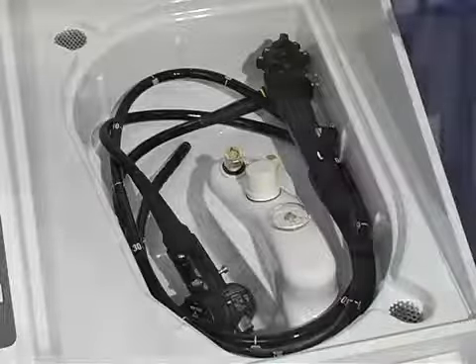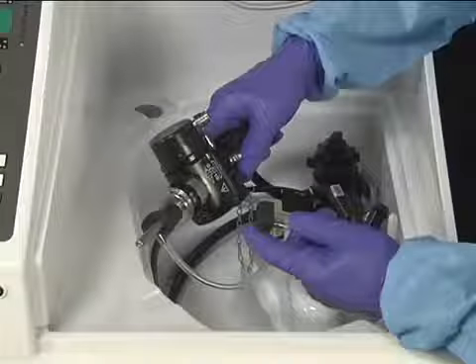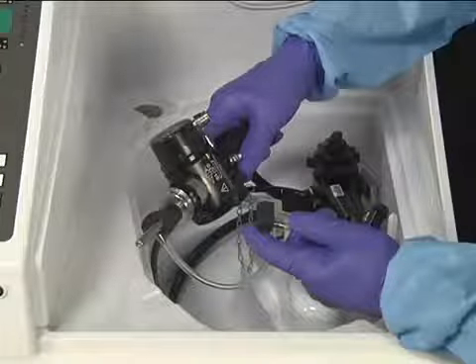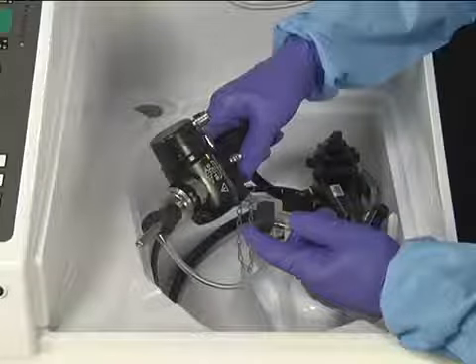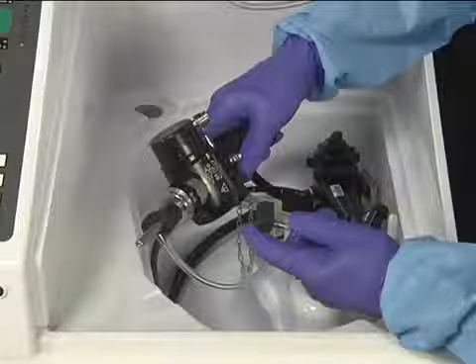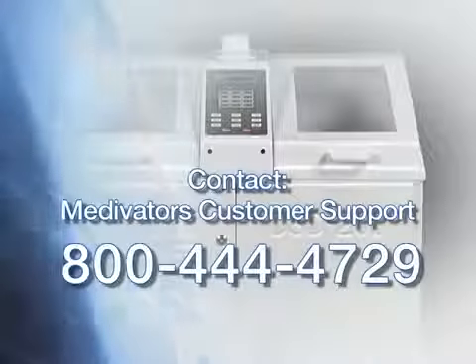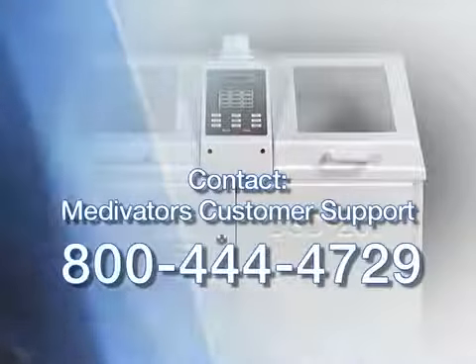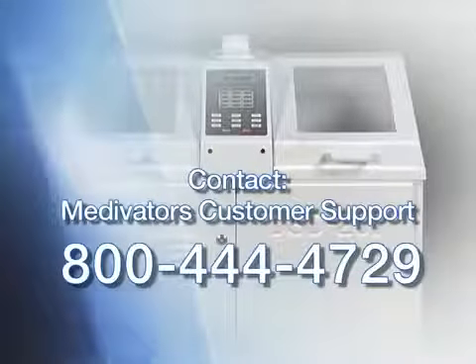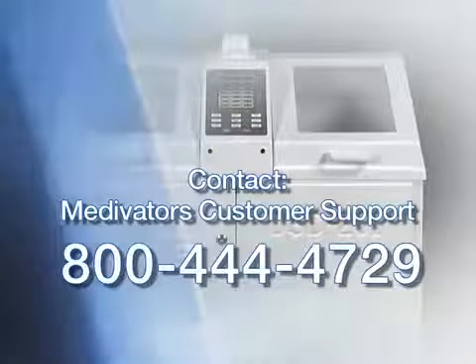The distal end should be positioned so that fluids passing through it into the basin will be clearly visible. The distal end needs to be tucked under the scope to ensure that water or disinfectant doesn't shoot up onto the floating lid. Endoscope channel connectors must be purchased along with your DSD-201. Matching the scope to the correct connector is critical to proper reprocessing of the endoscope.